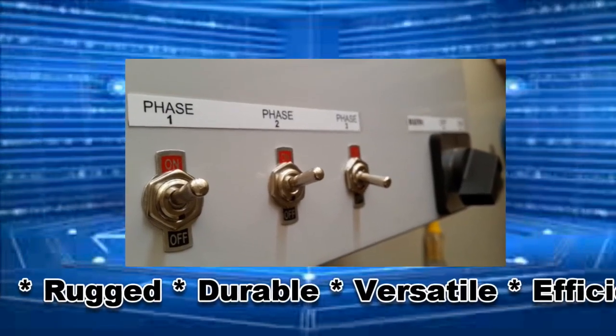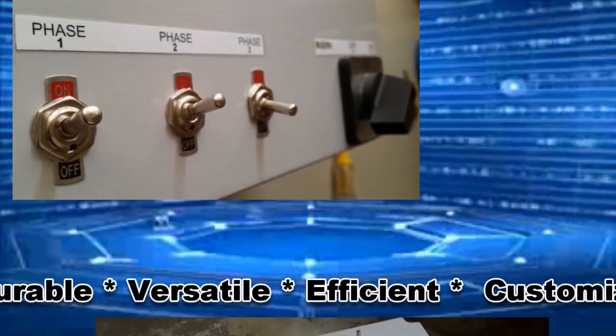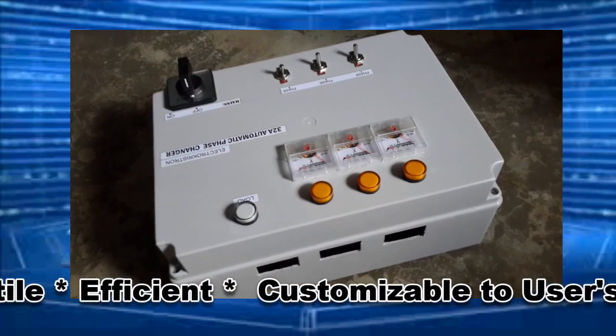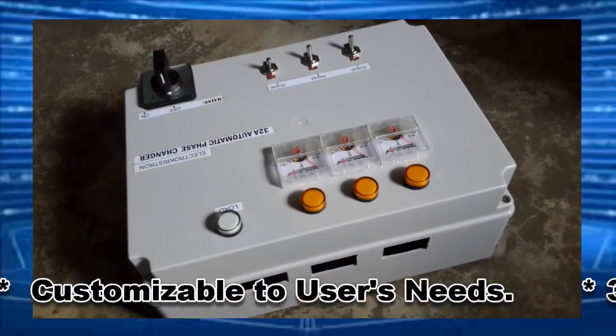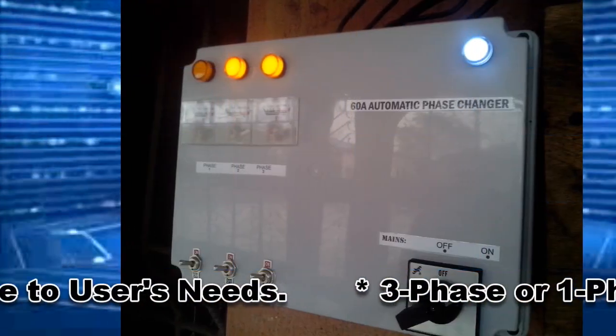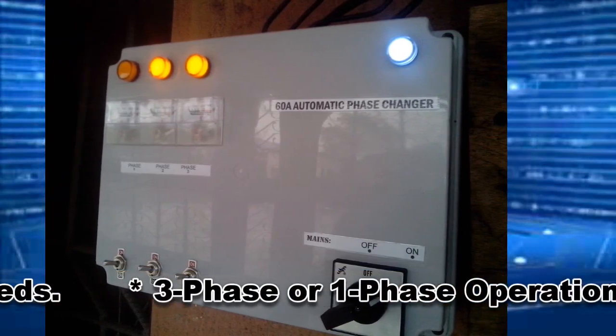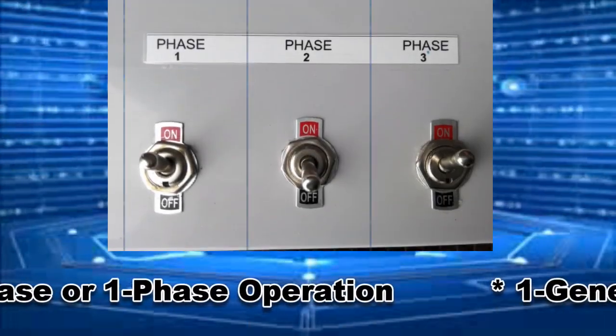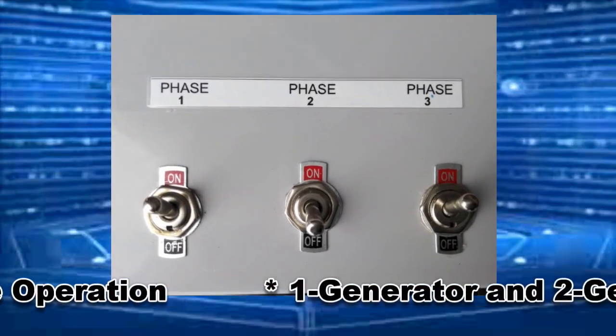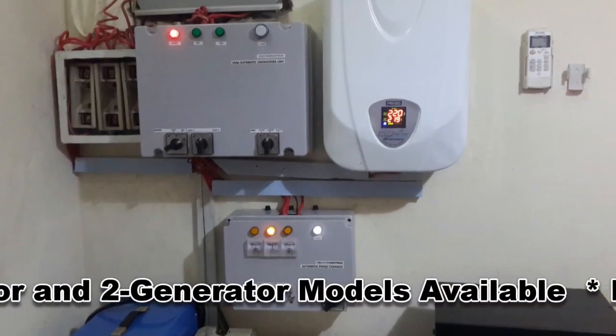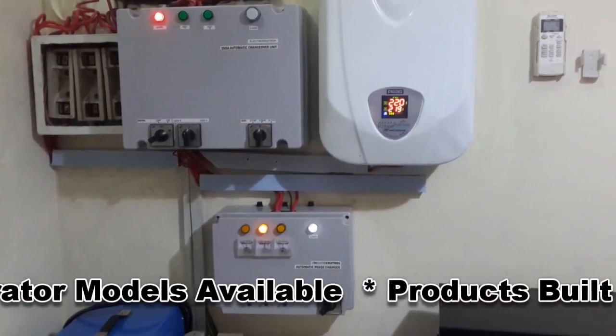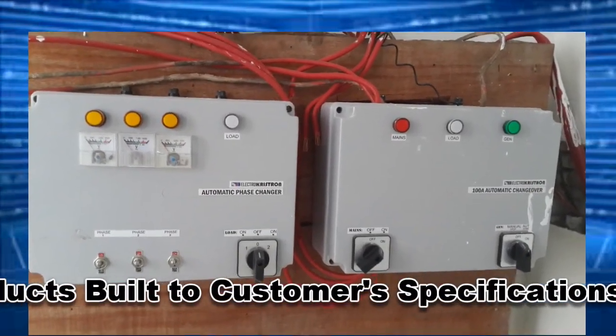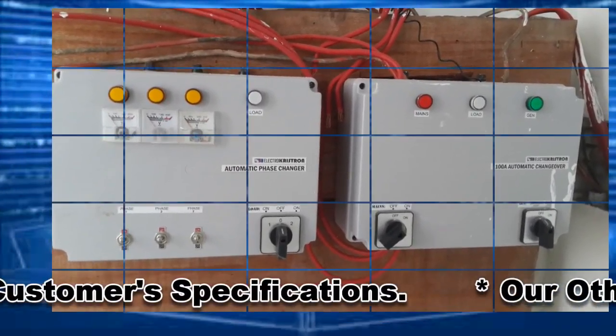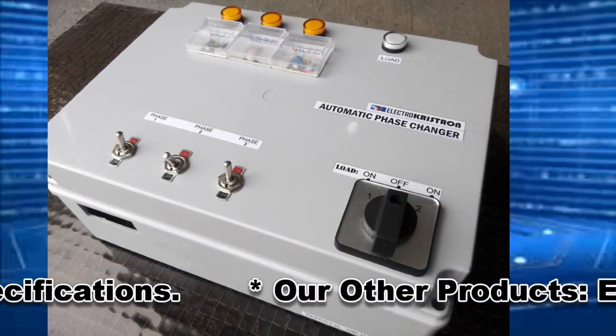Okay. Now we also have the Electrokristron inverter interface module, which connects the automatic changeover to your inverter, so that as soon as your inverter batteries begin to run dangerously low, then the automatic changeover will command your generator to start running. In other words, it will start your gen so as to charge your inverter batteries.